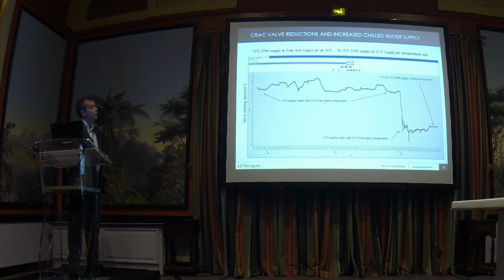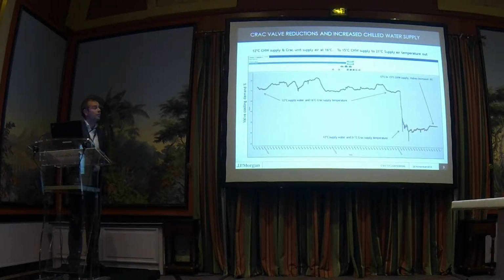So as we went along, 12 degrees supply water, and then the CRAC unit supply temperature is at 16. So we come across here, still got 12 degrees supply water to the CRAC unit, but then I've put the temperature up to 21 supply out of the machine. And we've just gone from 70 down to about 30%.